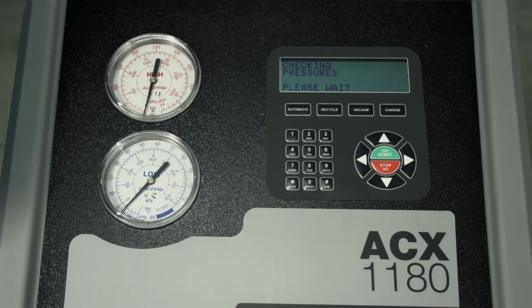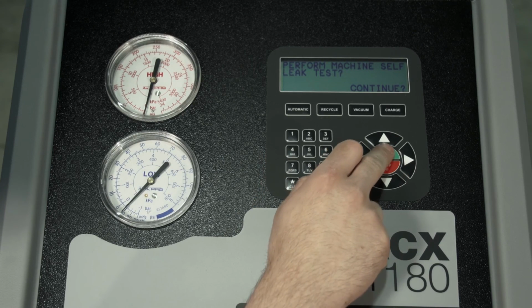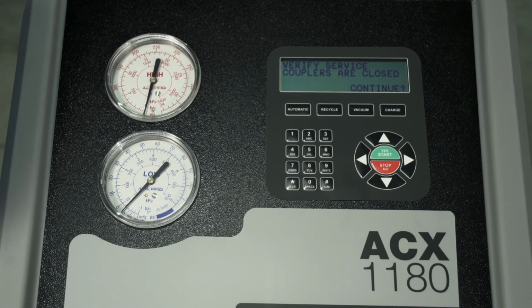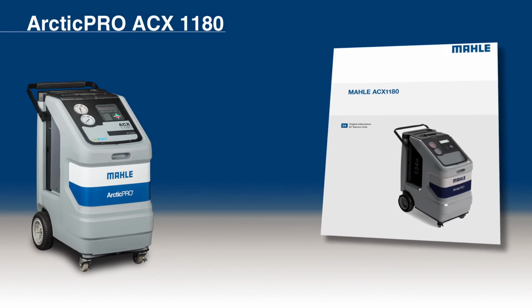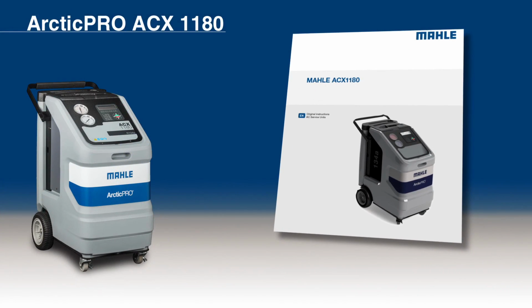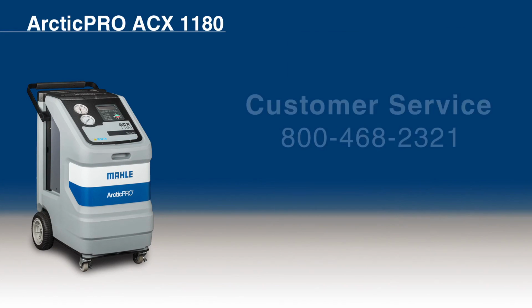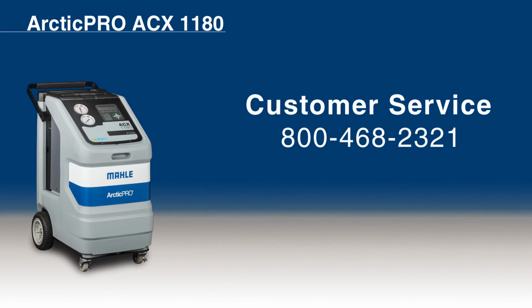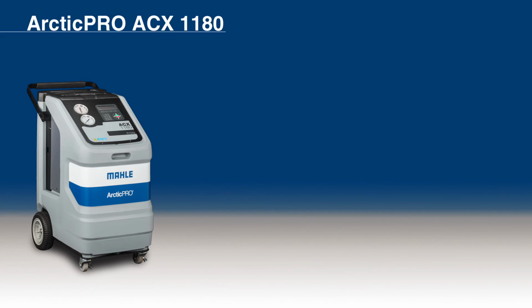Press Yes to continue. The machine will perform a pressure check and then prompt you to replace the filter. Press Yes again. The machine will then ask you, Perform Machine Self-Leak Test. Select Yes to continue. Follow the on-screen prompts to complete the test. Refer to the owner's manual for any troubleshooting. Never perform any maintenance work which is not expressly recommended in the owner's manual. Contact customer service if any components have to be replaced other than in the course of maintenance work. That concludes the maintenance instruction.